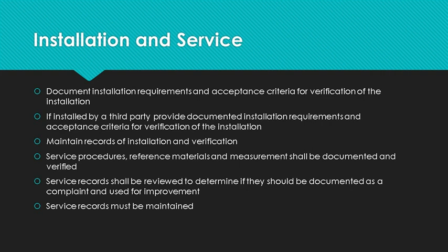We're almost through with production and service provision. All we have left is installation and service. These are sections frequently considered as not applicable; however, if you have a helpline, that is considered a service operation. Both installation and service activities must be documented with procedures explaining how to install the device and how to determine if it is functioning properly. If someone outside your organization is doing the installation, activities must be clearly defined along with acceptance criteria. If you or your supplier install the device, you must maintain records of the installation and the verification. Service records must be maintained and reviewed to see if they should be documented as a complaint or used to create improvement.